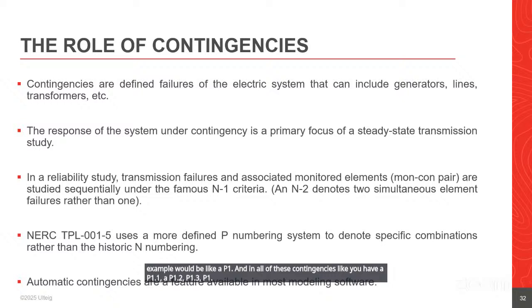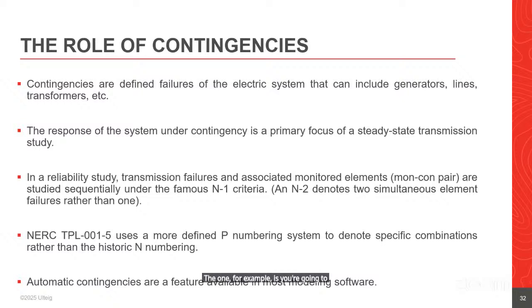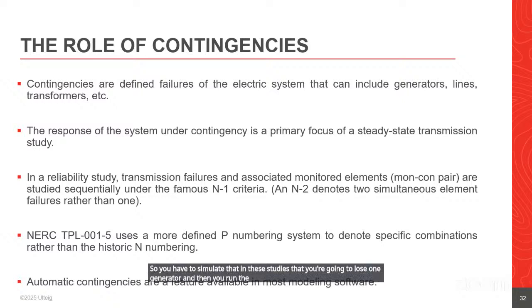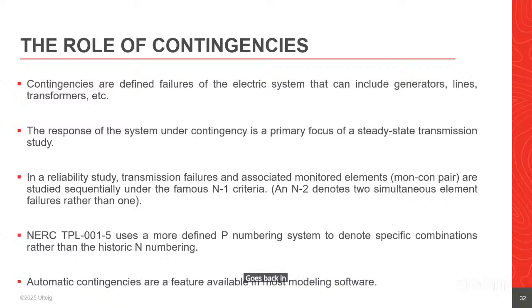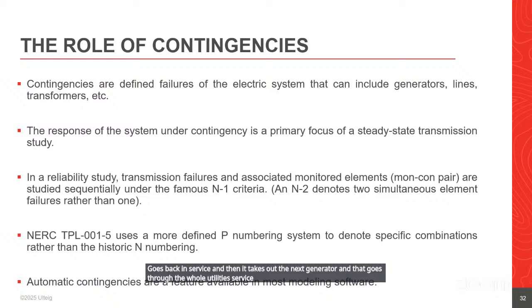Those sub numbers mean, for example, P1.1 is where you're going to simulate losing a generator. You have to simulate in these studies that you lose one generator, and then you run the analysis, and you're looking at thermal overloads, what happens, and you're looking at voltage analysis, what happens. Then you put that generator back in service, and it takes out the next generator. And that goes through the whole utility's service territory that you're studying.